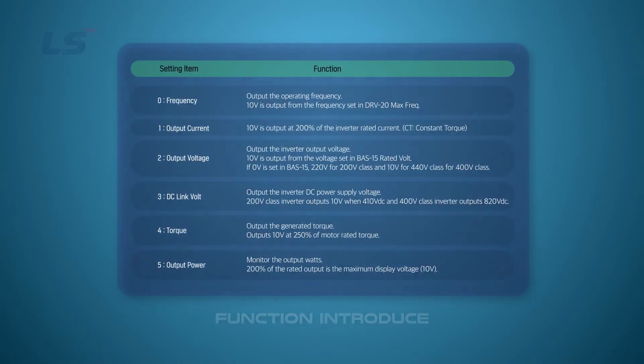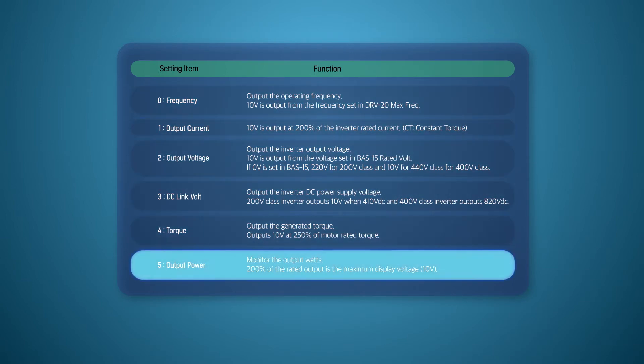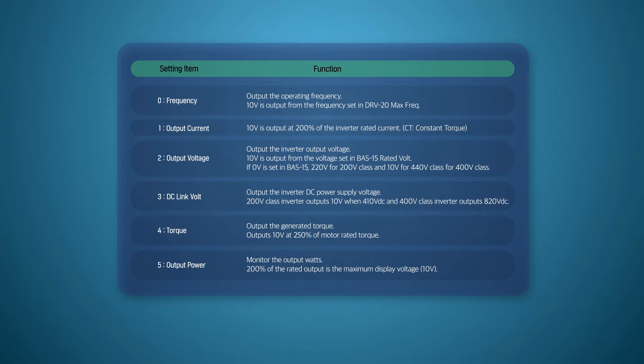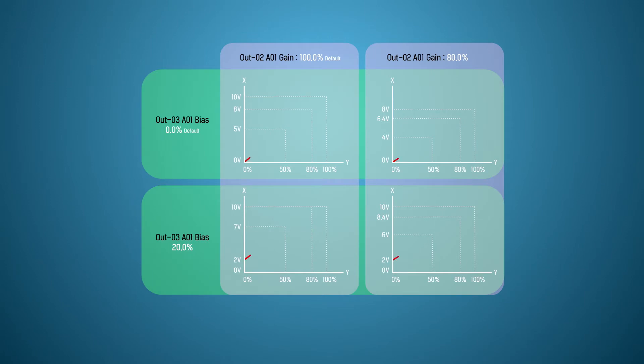The analog output is the same. The multifunctional analog output terminals, such as the AO1 and AO2 terminals, allow drive operation information, such as output frequency and output current, to be converted to voltage or current. You can also resize the actual output voltage or current according to the output value.